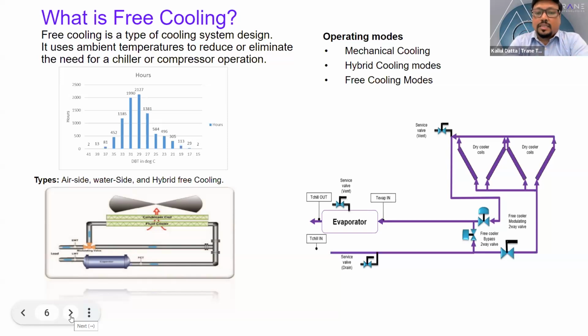Assume there is a typical data center. We are designing a refrigeration system or air conditioning product or HVAC system, where the data center requires around 27-degree chilled water leaving temperature. Now, for better water use effectiveness, we can always design a data center at 10-degree delta T. And if we design chilled water leaving at 27 and return water temperature of 37, how does this free cooling affect the chillers?